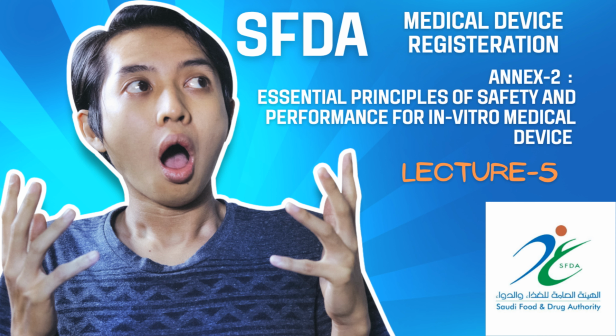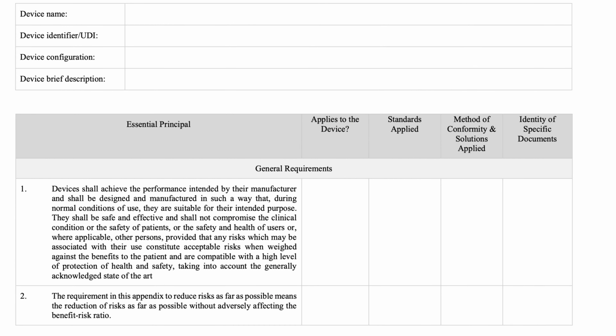So my friends, first of all you need to publish or state the full information, which is the device name, UDI, device configuration, and the device brief description. When you see the requirements, the general requirement and the design requirement, those two requirements are much more similar to the medical device requirement.